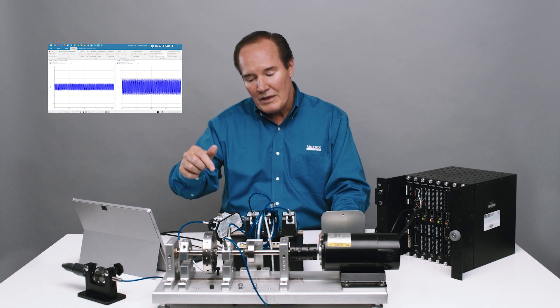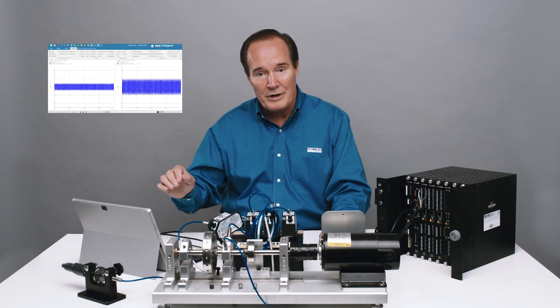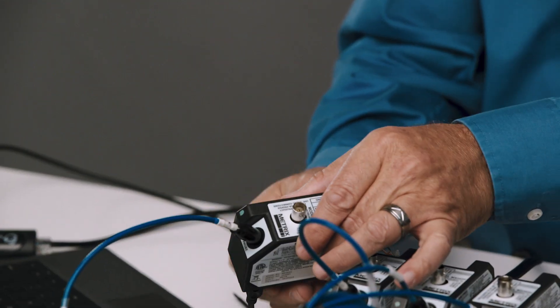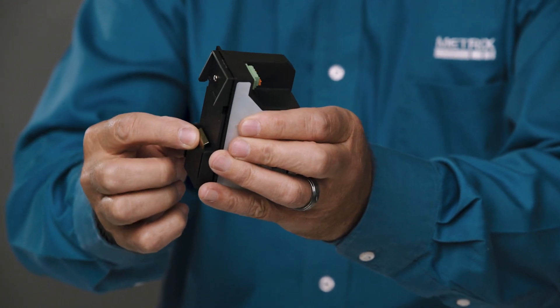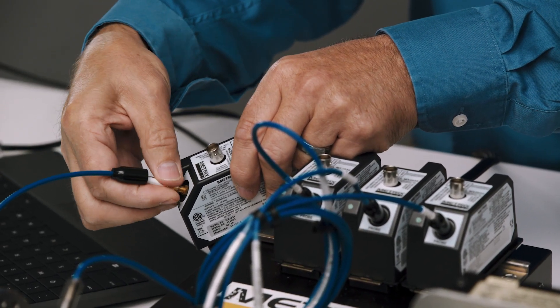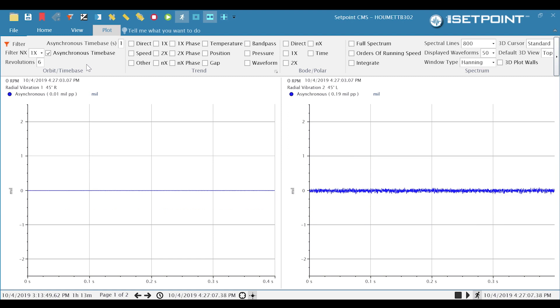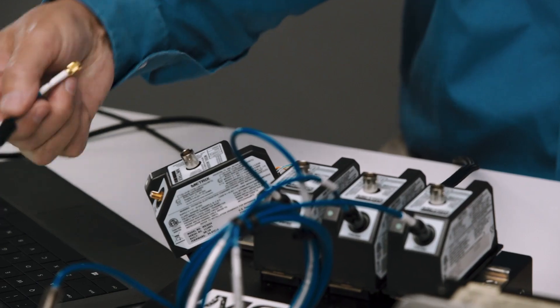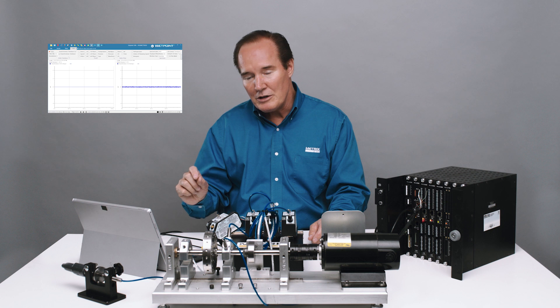What I'm going to do is disconnect the Y transducer — radial vibration one — and we should see radial vibration one go to zero because it's really not vibrating. I've removed the DIN rail mounting screws so I can get to the USB port to change the frequency and use crosstalk elimination. So I'm going to disconnect this transducer and we'll see that signal go away. You can see that radial vibration one went to absolutely zero — there's nothing on it because it's totally disconnected. And on channel two, we've got a little bit of background noise: 0.2 mils peak to peak. So that's not bad — that's really acceptable ambient noise for a transmitter.